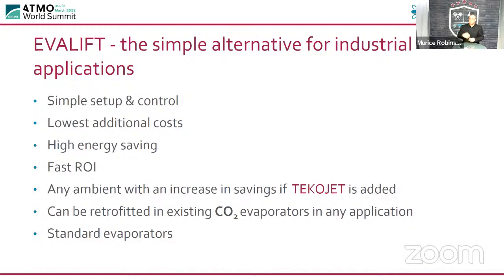Obviously, if you add the TEKO Jet in very high ambient conditions, then we can get a much greater benefit. However, in the standard applications and in large applications, you're going to have the best energy savings. The system can also be retrofitted to any CO2 evaporators as well. So you don't have to worry about special evaporators. In the initial design, it would be nice to be able to size the evaporators and design them correctly for flooded or semi-flooded applications. But it's not necessary whatsoever. You can use standard evaporators, no problem at all.